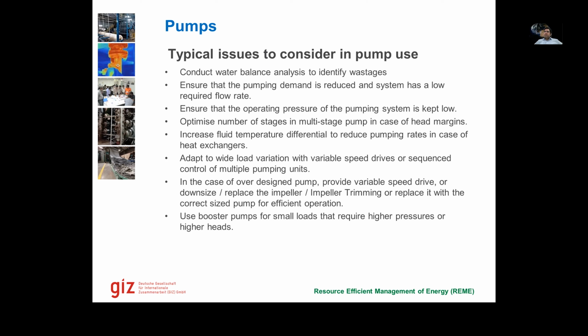Recently, we saw a case where the factory even skipped some pumps. They did the schematic diagramming of all the pumping circuits, and they figured out that they have too many tanks in between. They pump the water from one area to another, then they have a tank, then they pump it again, then another tank, and then they pump it again. So they did some sequencing and piping redesign and removed the tanks in the middle. They kept only one tank that was needed for the demand side. This way, they were able to remove two pumps from the line. So rather than running three pumps, they were running only one pump, and that too was equipped with a variable frequency drive. So they saved a lot of energy in pumping.